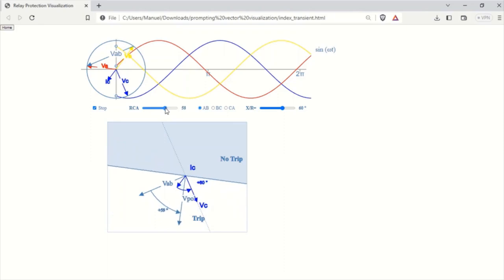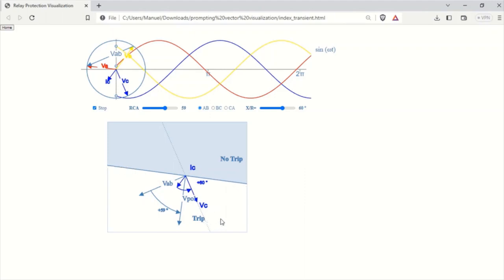To give directionality to the overcurrent relay and determine whether to send a trip signal to the circuit breaker, an orthogonal line is drawn to the polarizing voltage defining a trip and no trip zone. These zones are color coded for easy differentiation with the no trip zone indicated by light blue.